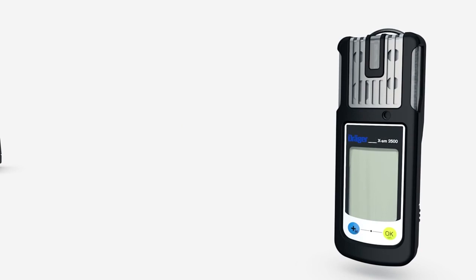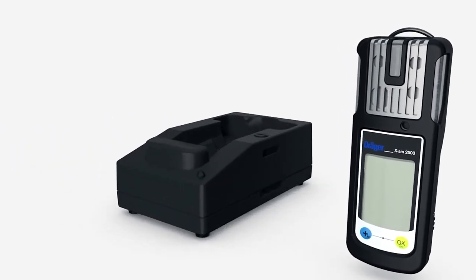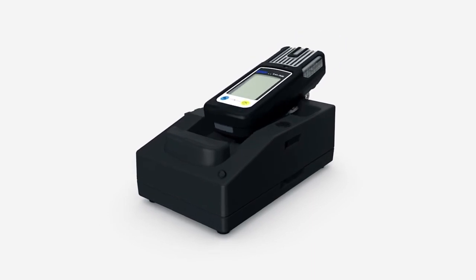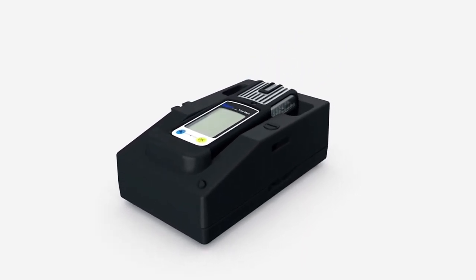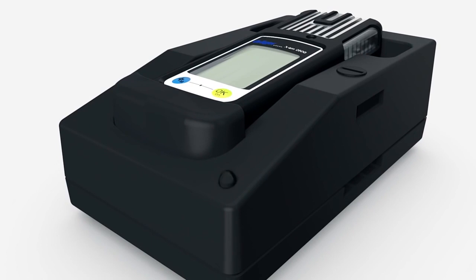The Dräger X-am 2500 uses either a nickel metal hydride battery or alkaline batteries. If you use your Dräger X-am 2500 with rechargeable batteries, recharge it in the charger, which can also be used in a vehicle using the vehicle charger mounting kit. Place the instrument inside the charger. If the red LED is flashing, the device is still charging. If the light is on continuously, the device is fully charged. Charging takes about four hours.